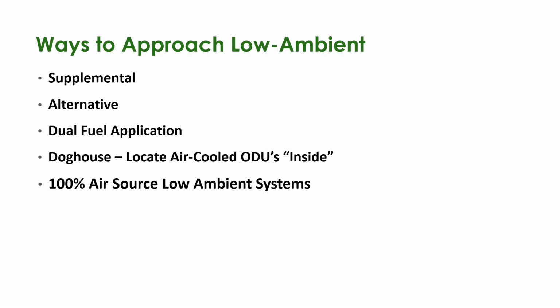So just in review, ways to approach low ambient climate design. Supplemental is probably the first go-to in most of the mild or cold climates. Alternative is, in my experience, the most commonly used. That way you have both supplemental and the ability to switch the entire system off and switch to an alternate fuel source or switch straight over to electric. Dual fuel applications, either through manufactured strategy or third-party integration DX kits, or doghouse, locating the air-cooled units inside. And most recently and more commonly these days is, if the environment allows for it, 100% air source, low ambient systems, or the enhanced capacity systems.